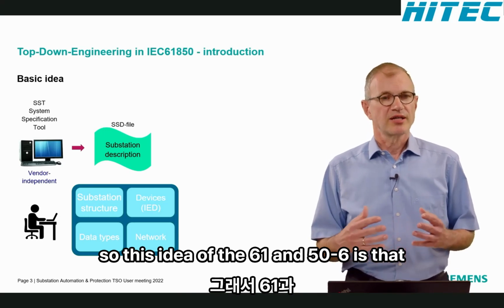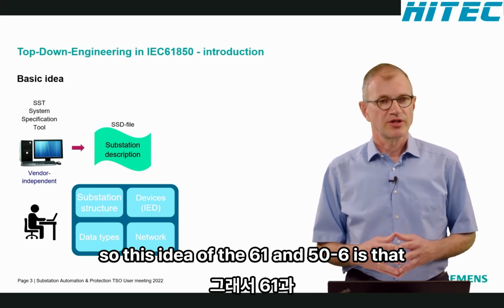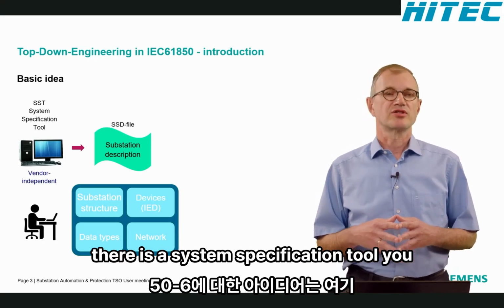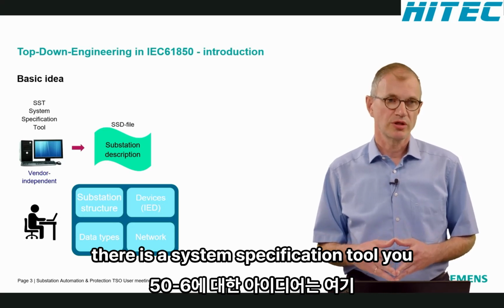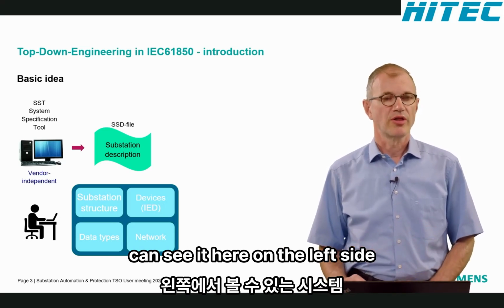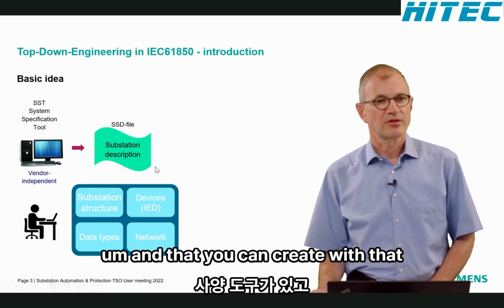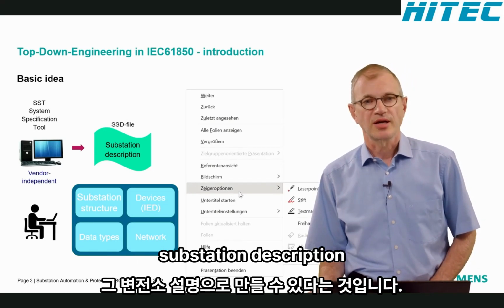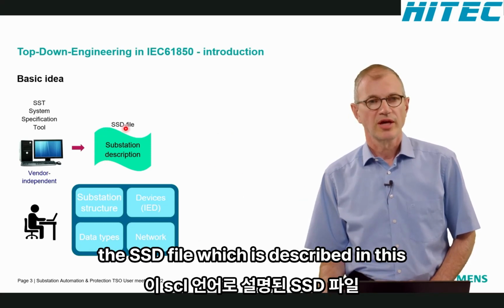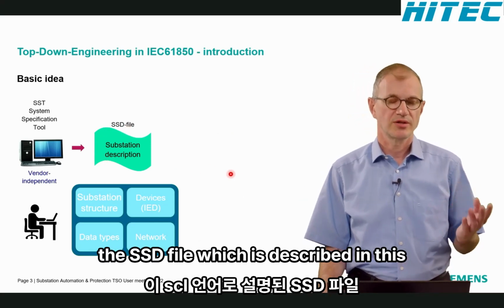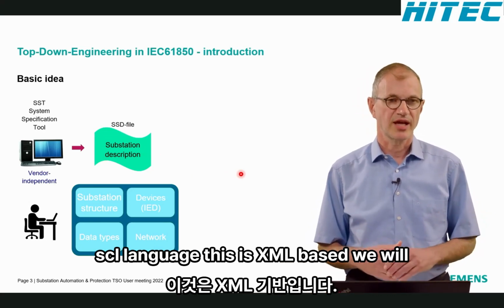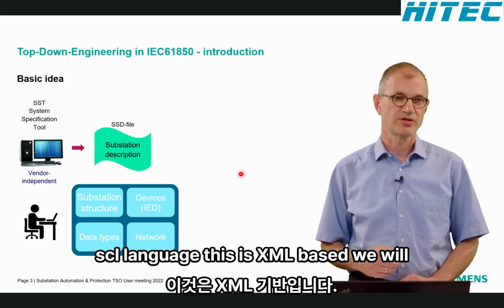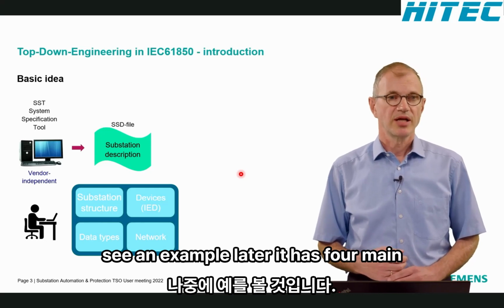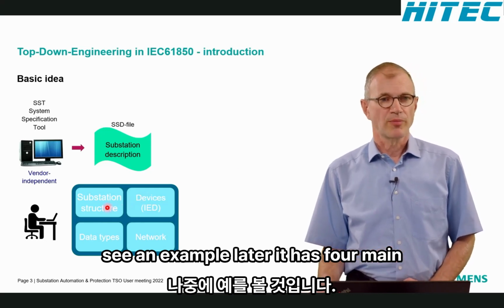So this idea of the 61850-6 is that there is a system specification tool. You can see it here on the left side, and that you can create with that a substation description. The SSD file, which is described in this SCL language. This is XML based. We will see an example later. It has 4 main parts.